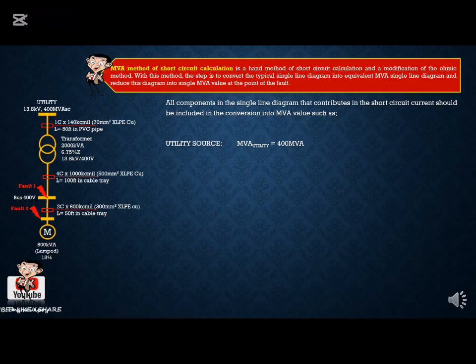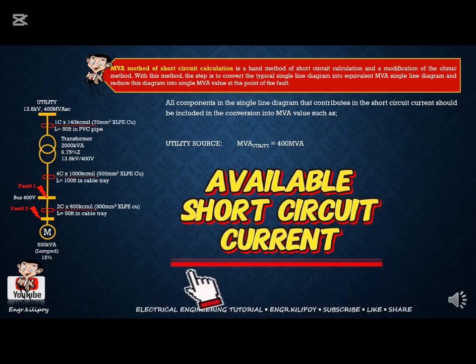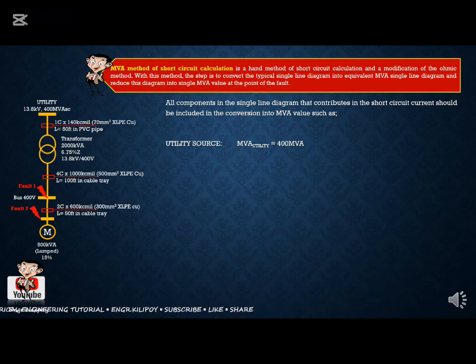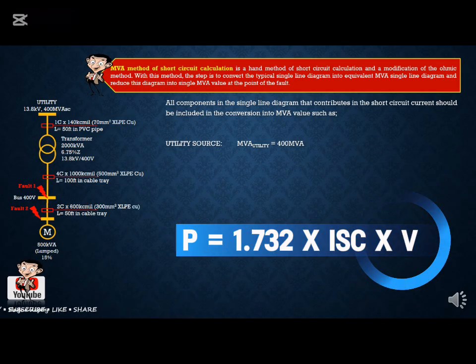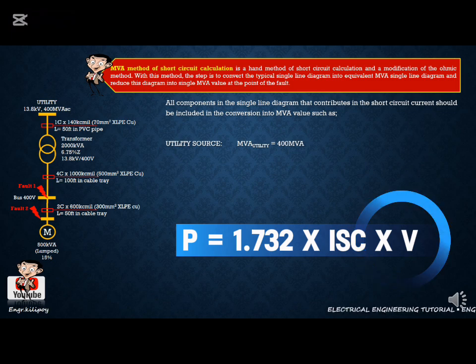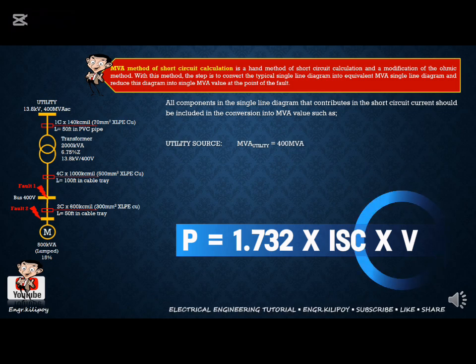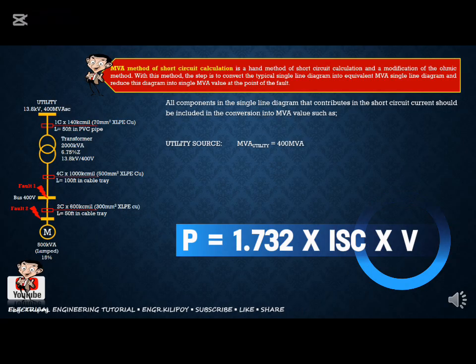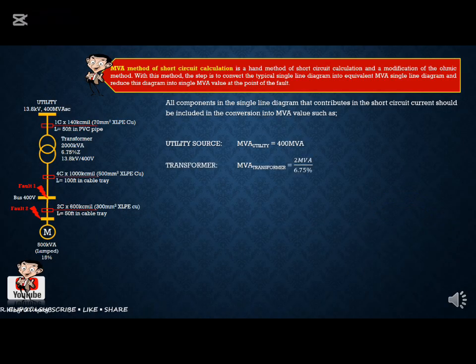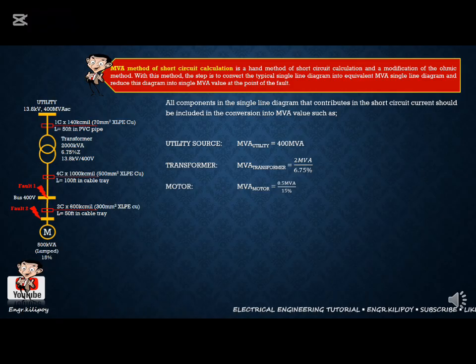So if your data is the available short circuit current, you can use the power formula: square root of 3 multiplied by the short circuit current multiplied by the utility voltage. So that is the MVA of the utility. For the transformer, you can say that this is 2 MVA divided by 6.75%. For the motor, it's 0.5 MVA over the 15% subtransient value.